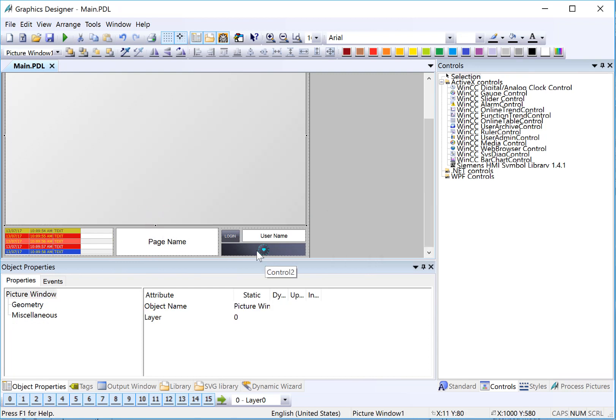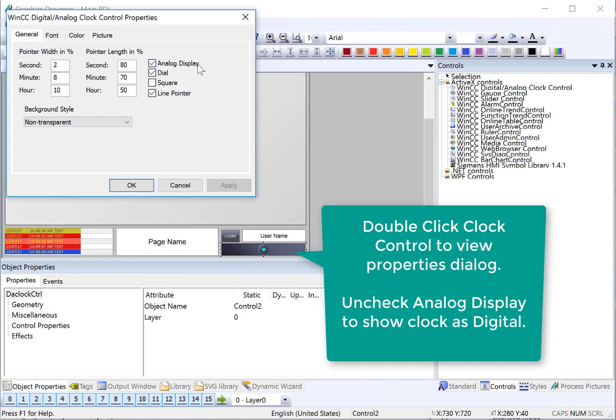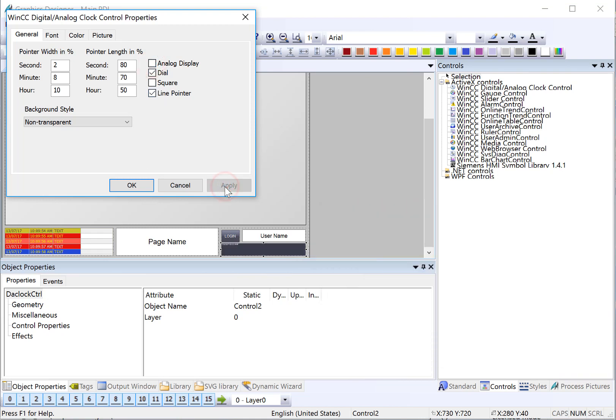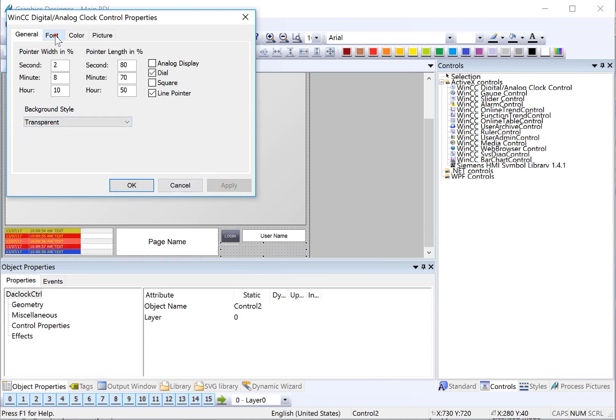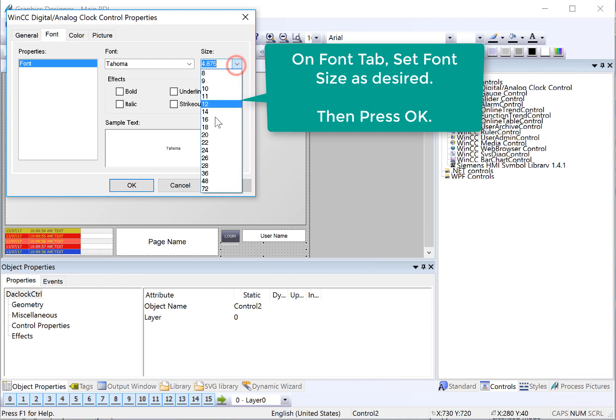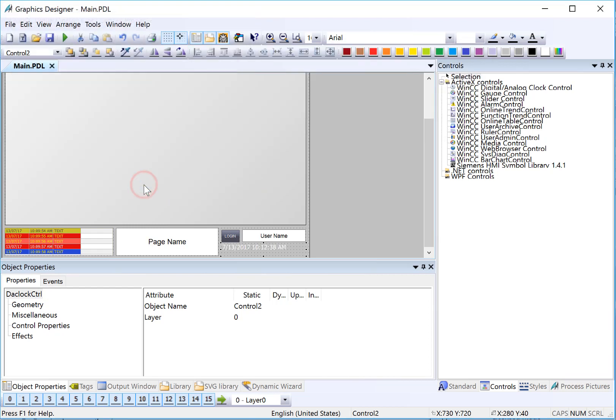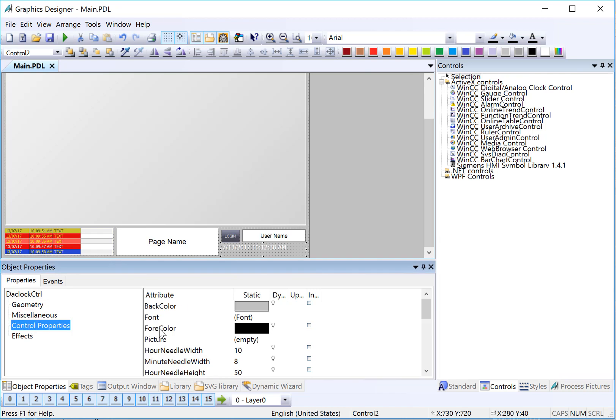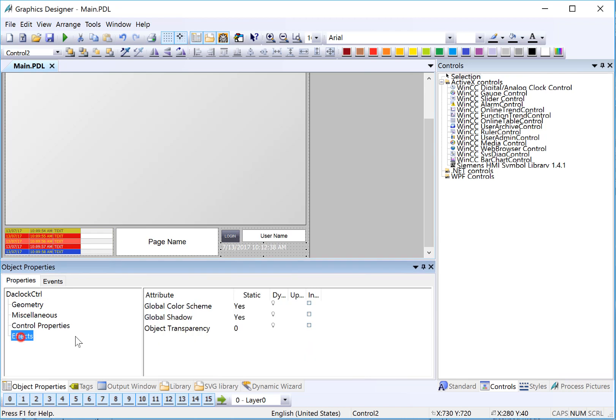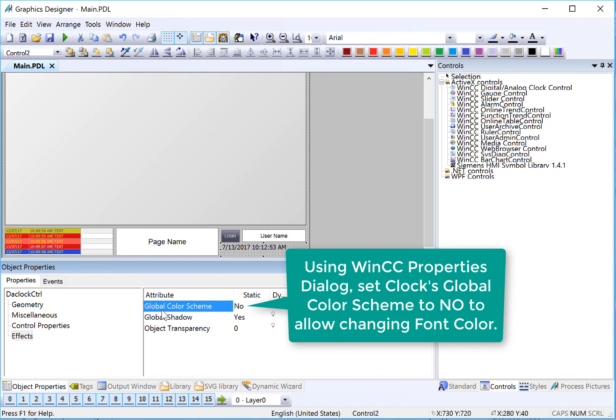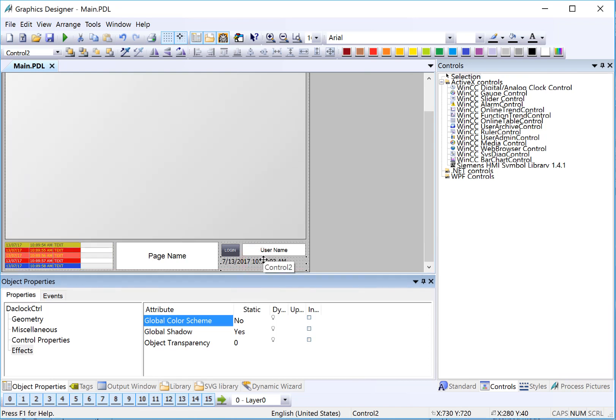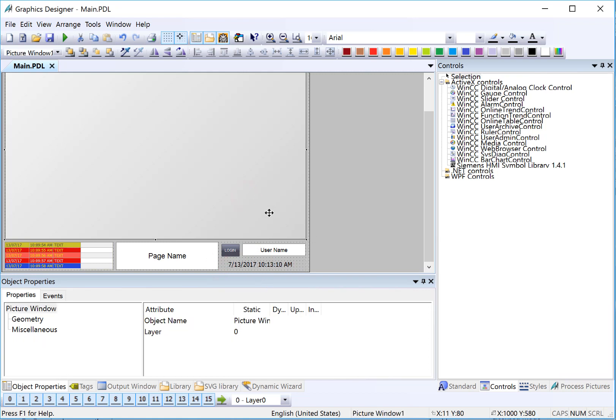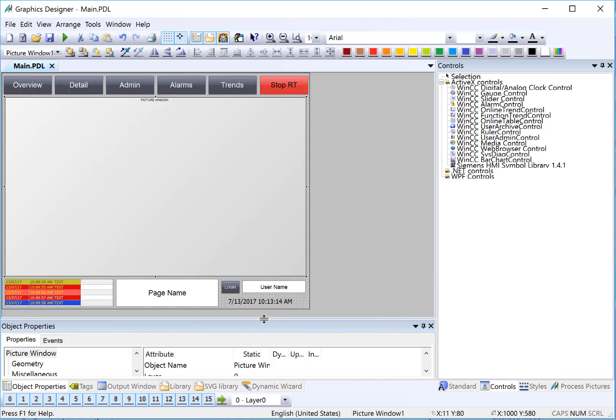So next, we're going to make this look like a digital clock. So I'm going to double click. And since it's an ActiveX, it's going to give me the ActiveX properties. I'm going to uncheck analog display and hit apply. And then I'm going to set my background style as transparent. And then on my font size, we're going to give it something that we can see. I can also use the WinCC properties dialog. So if the clock is selected, I can go to control properties. And I have to turn off my global color scheme in order to be able to change those properties. So make sure you do that. And then it shows in a nice black font by default. There's not an alignment property. So I'm just going to change the size and shape of this since it's transparent to make it appear aligned. And then I'll pull this down. And that's what our main screen looks like.